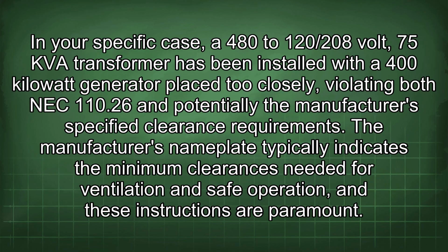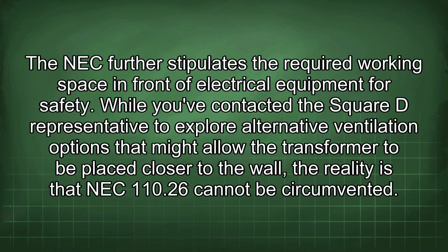In your specific case, a 480 to 120/208 volt 75 kVA transformer has been installed with a 400 kilowatt generator placed too closely, violating both NEC 110.26 and potentially the manufacturer's specified clearance requirements. The manufacturer's nameplate typically indicates the minimum clearances needed for ventilation and safe operation, and these instructions are paramount. The NEC further stipulates the required working space in front of electrical equipment for safety.